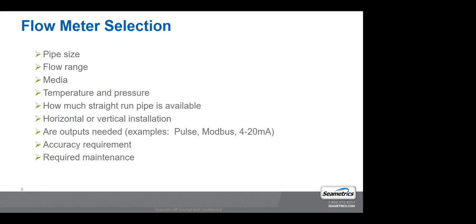How much straight run pipe is available? Is it a horizontal or vertical installation? That impacts some technologies, others it does not. And do you need outputs on it? So some of the outputs that are common in irrigation are pulse. We're seeing more and more demand for a Modbus output. And 4 to 20 is not quite as common, but we do see some of it in irrigation.